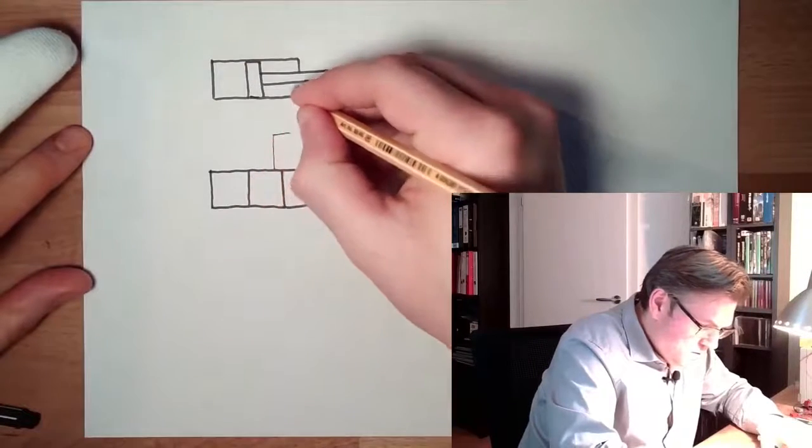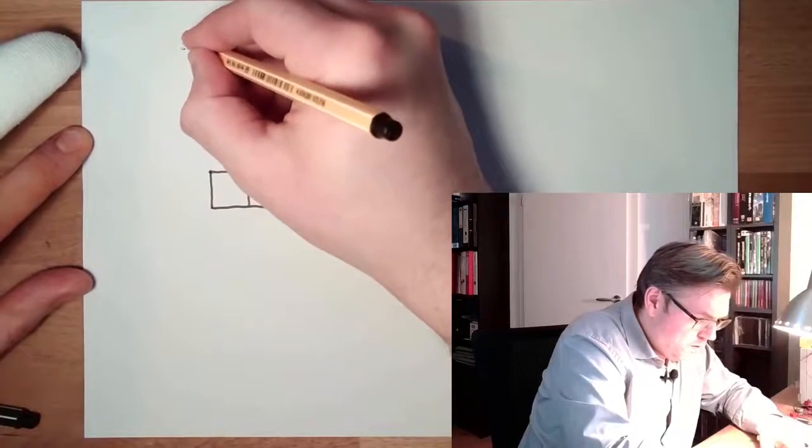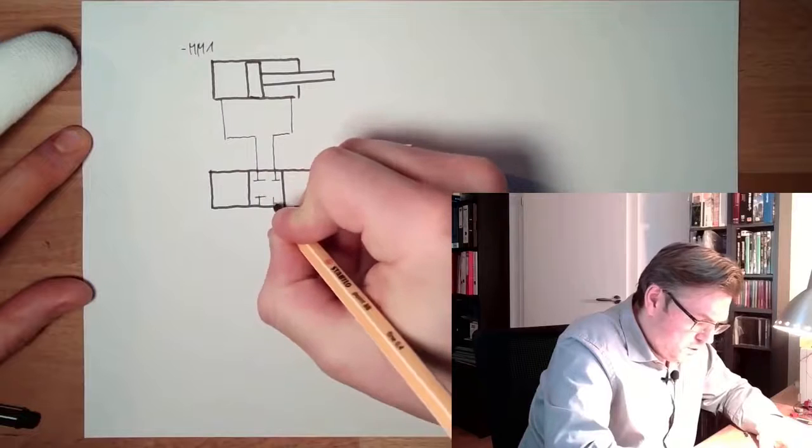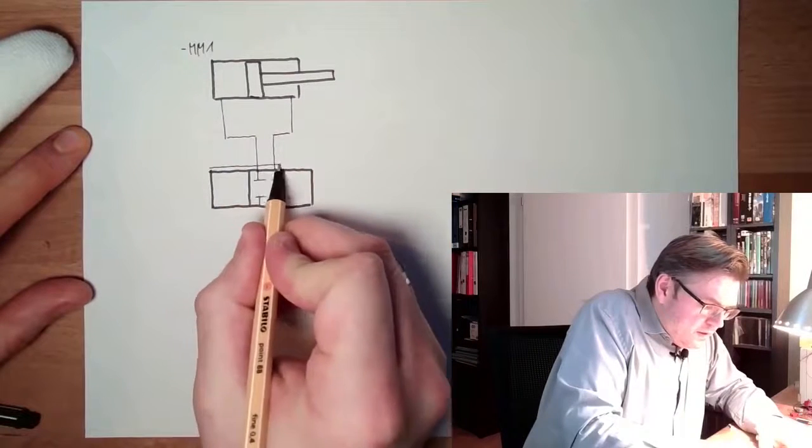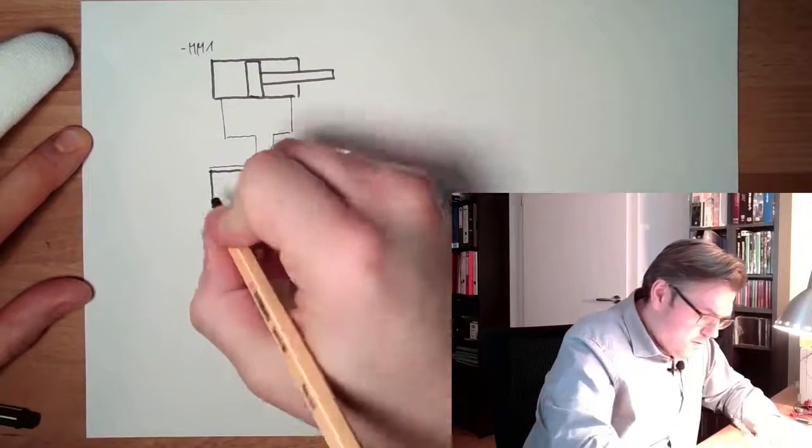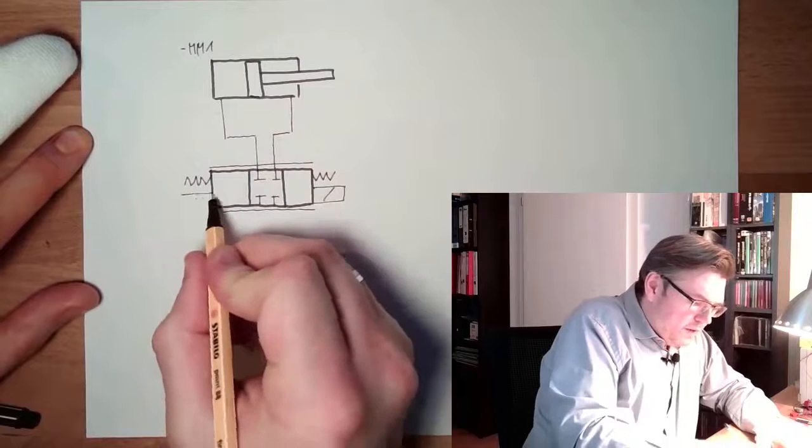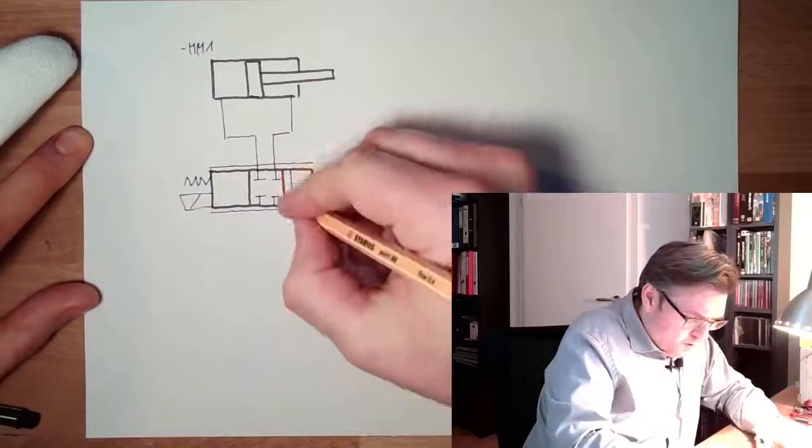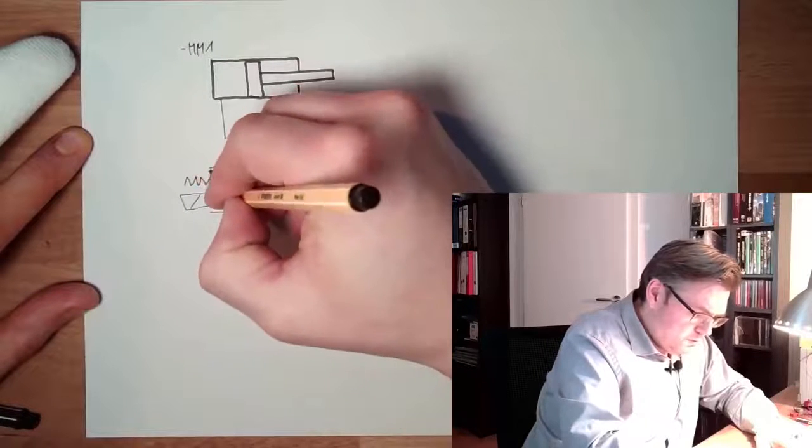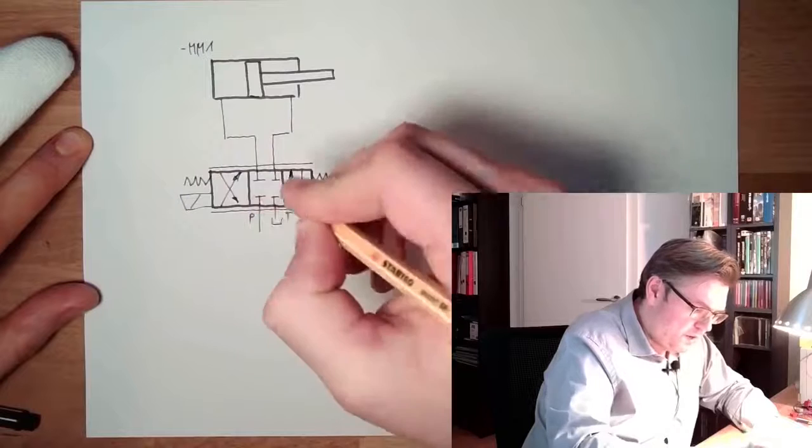This is connected to the cylinder MM1. Here in the middle position, we have blocked position everywhere. And like I said, this is a proportional valve. Middle position with springs operated by proportional magnets. One is straight position, the other one is the cross position. See here we go to the tank, that's the pressure line, that's A and B.